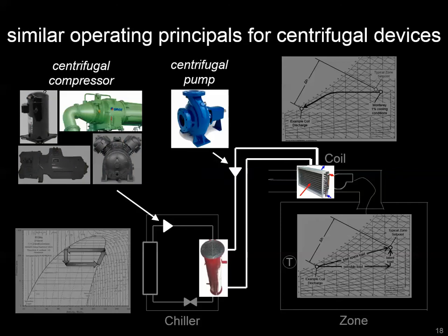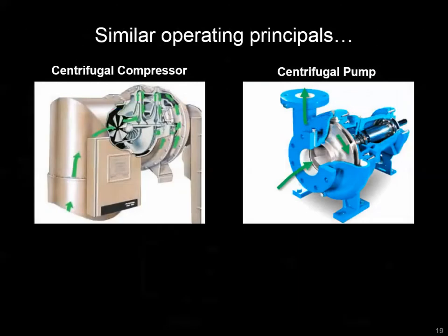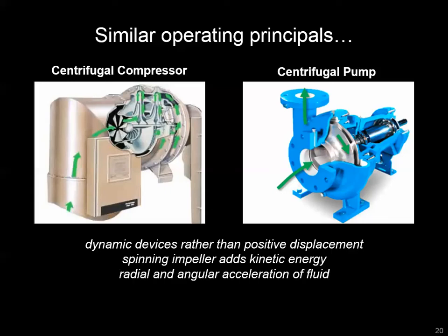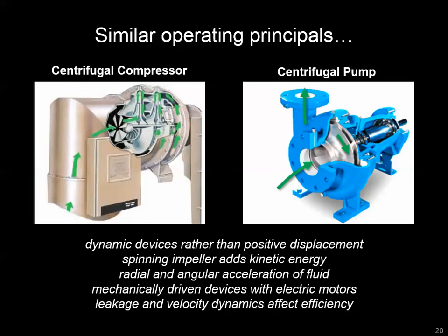The centrifugal pump has a lot of similarities with the centrifugal compressor. First, they're both dynamic devices — rather than being a positive displacement or piston-style compressor or pump — which means you have a spinning device called an impeller that accelerates and pressurizes the fluid. Both are driven by an electric motor, and because of their shape, geometry, and operation, they share similar efficiency characteristics and hydraulic losses.